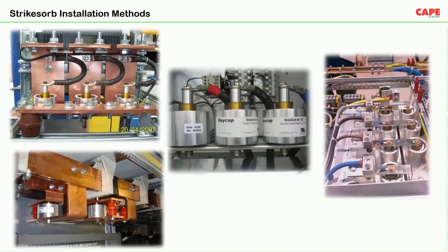These are the various connection examples for bus-bar-mounted SPDs. A separate earth bus bar can be made for their connection, or they can be connected directly on the phase bus bar. With this type of connection, since the SPD is mounted directly on the bus bar, the wire length is effectively zero — only a very short wire of perhaps 10 mm is required to connect the SPD body to the panel earth.